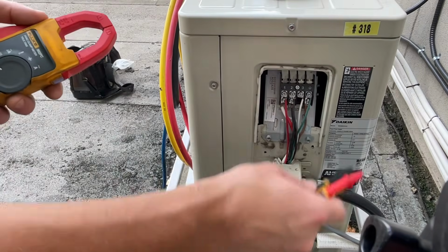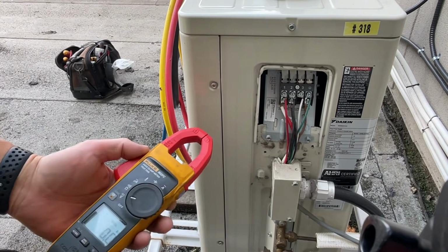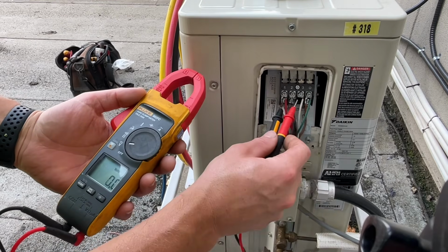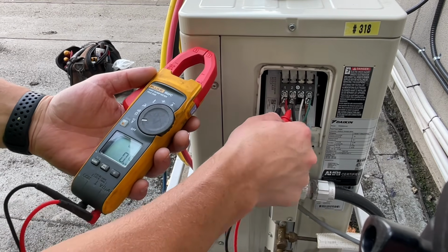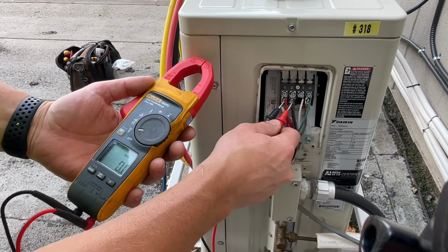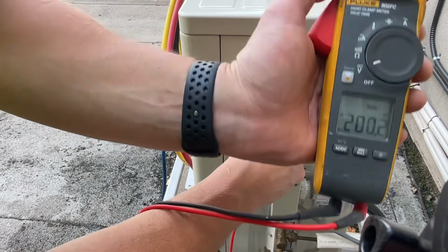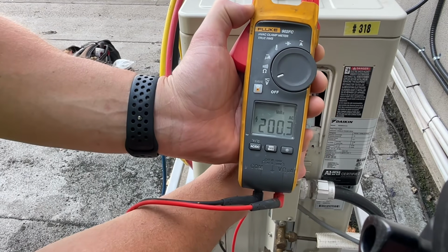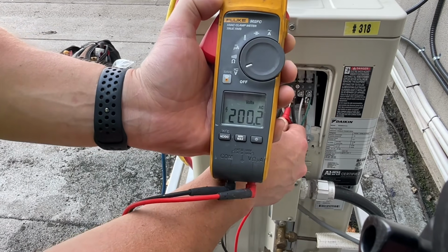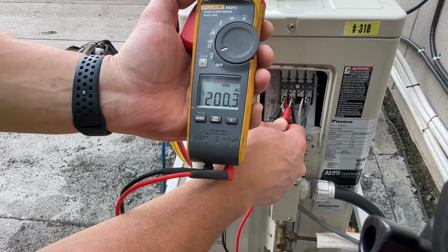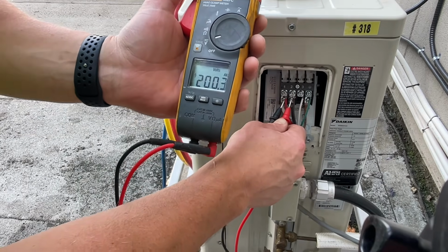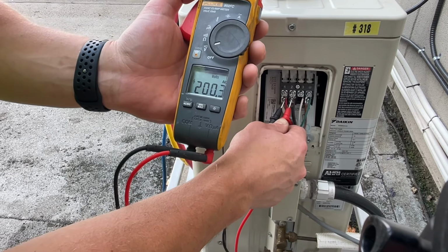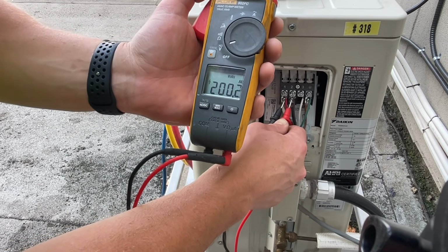All right, we've removed our side cover here for our unit. It's up and running as we speak, but let's double check our voltage here. Cool. So we have 200.3 volts, which is good. That's within our operating range. Next, we'll check our running pressures, and I'm probably gonna sum this up to a power failure they had here last week throughout the building. It might have generated that error code on the machine.